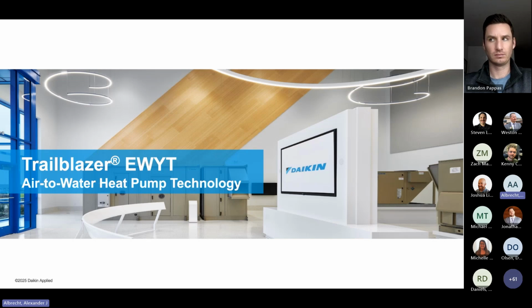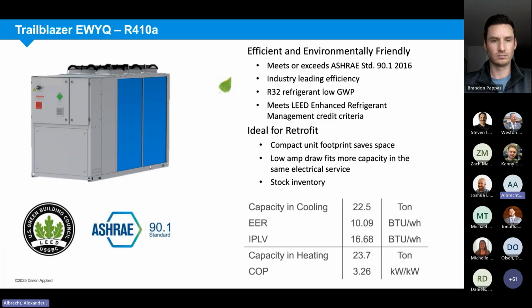This is a unit we purchase from our sister plant in Cecchina, Italy, and sell as stock from our Stanton plant, currently with both R410A and R32 refrigerant, carrying many of the advantages of R32 such as improved efficiency. It's a fixed speed 2-pipe design, capable of being piped in series up to 8 units for a total of 200 tons of capacity, ideal for retrofitting with small footprint, as well as quick turnkey ship-to-delivery with stock unit accessibility.